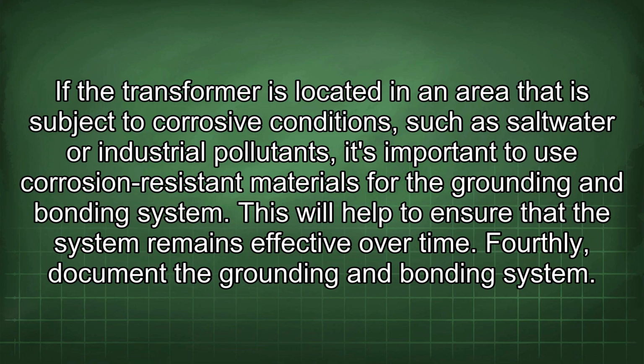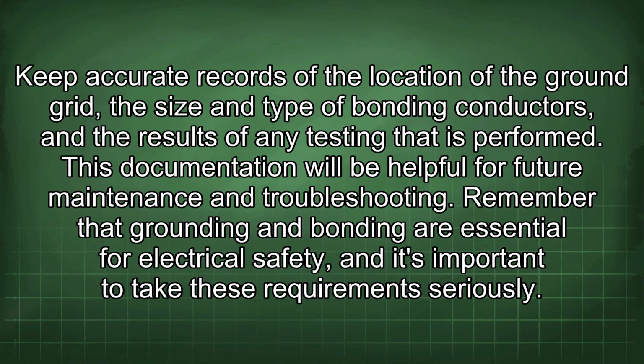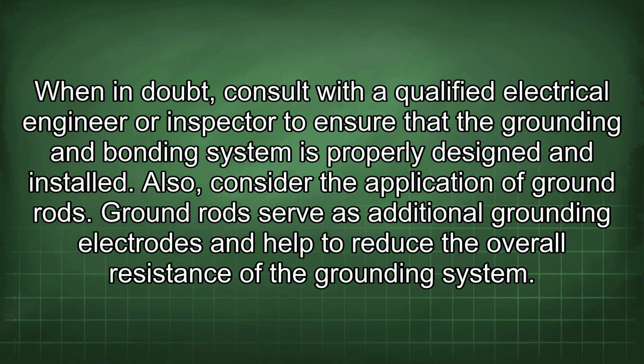Fourthly, document the grounding and bonding system. Keep accurate records of the location of the ground grid, the size and type of bonding conductors, and the results of any testing that is performed. This documentation will be helpful for future maintenance and troubleshooting. Remember that grounding and bonding are essential for electrical safety, and it's important to take these requirements seriously. When in doubt, consult with a qualified electrical engineer or inspector to ensure that the grounding and bonding system is properly designed and installed.